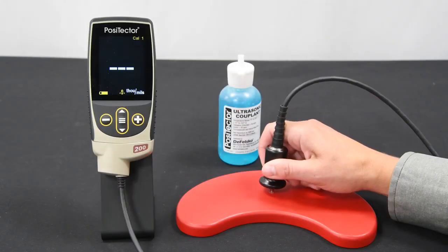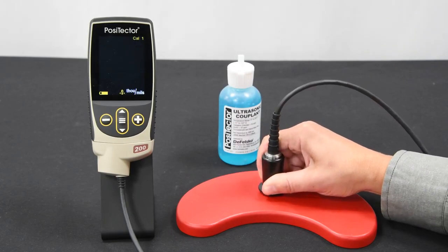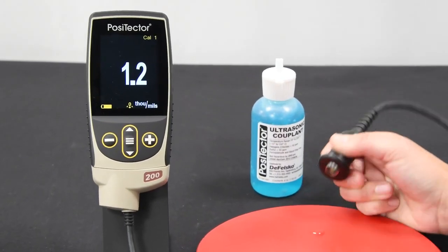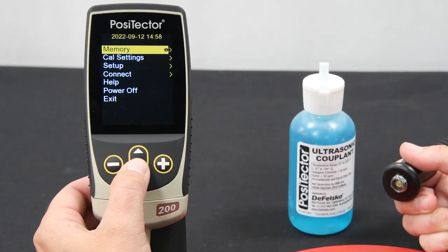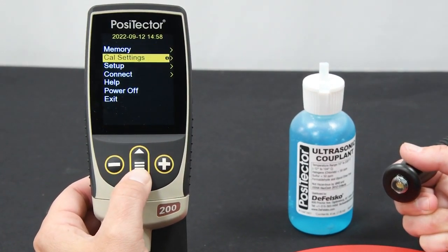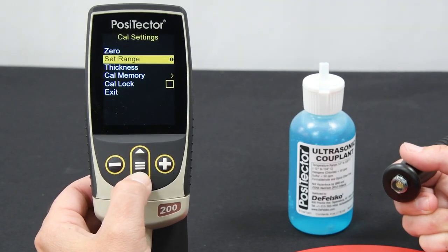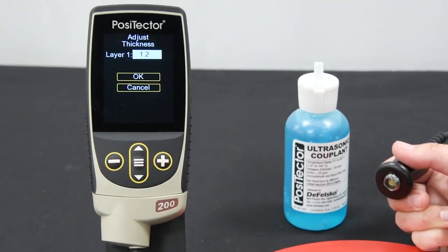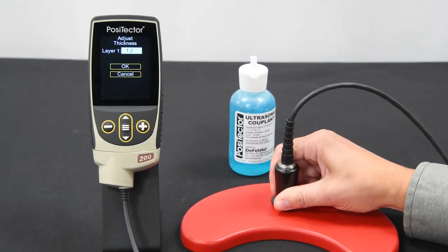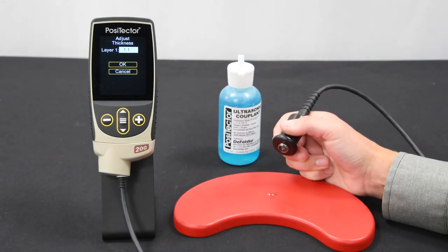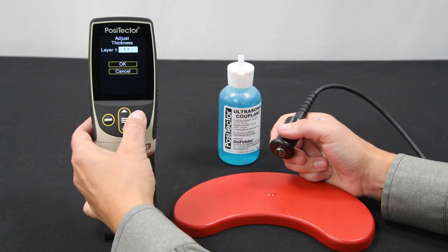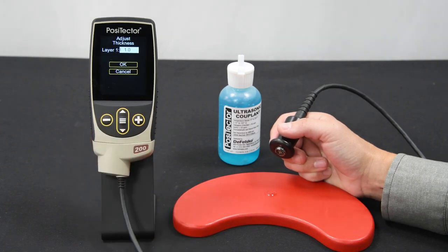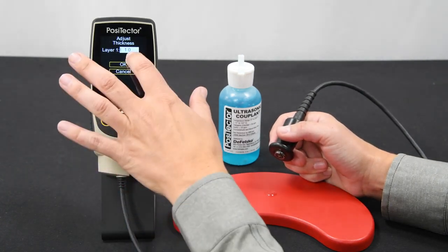adjustment required. To determine if an adjustment is necessary, measure a sample of known thickness. If the average of a series of readings is not close to the known thickness, a thickness adjustment should be made. To adjust to a known thickness, open the Cal Settings menu and select the Thickness menu option. Take a measurement on the sample and use the plus or minus buttons to increase or decrease the displayed measurement value to match its known thickness. To save adjustment, select OK.